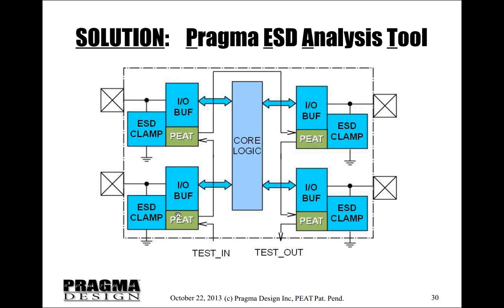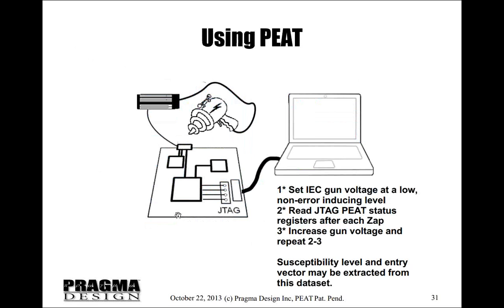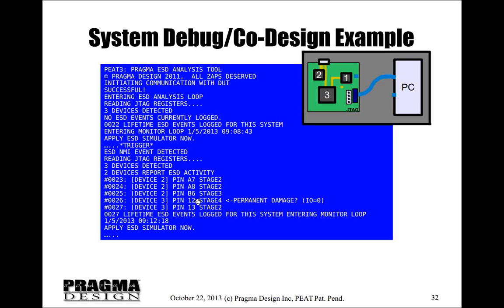And by doing that, imagine if you're kind of combining it with the way susceptibility scanning and current reconstruction work. Because if I take my little Buck Rogers ESD gun and hit the port at 1 kV and nothing happens, then at 2 kV I get a couple pins going off, and at 3 kV I get damage, say on pin 12, but some of these other pins are still getting activity without being damaged. Now I've got a map I can see on the board of what pins are getting hit and why, and I don't need a scanner.